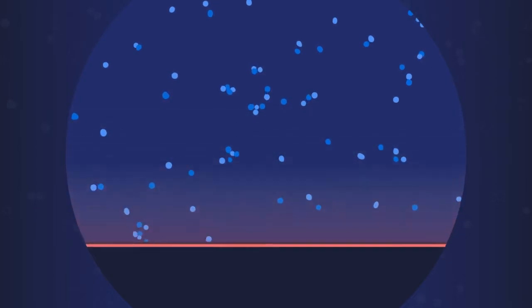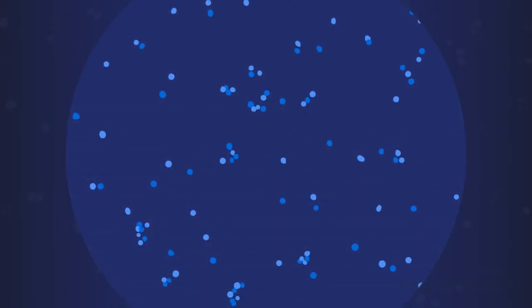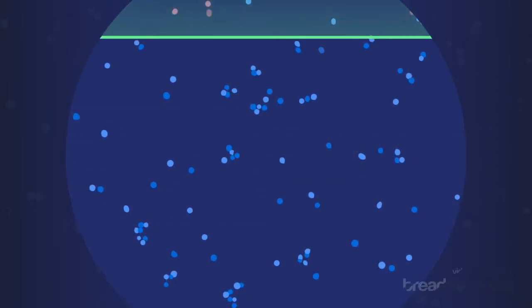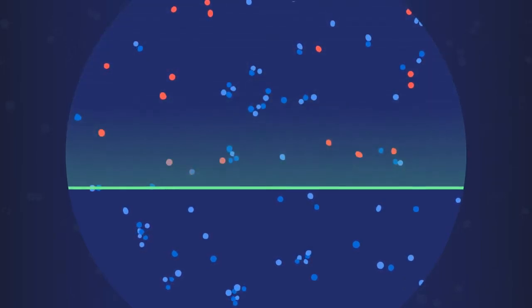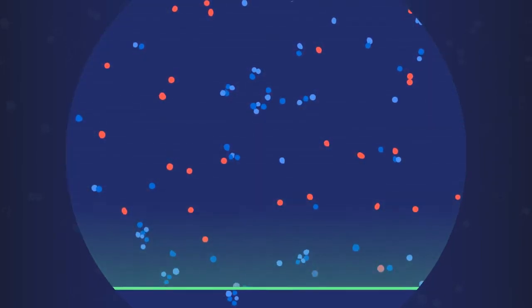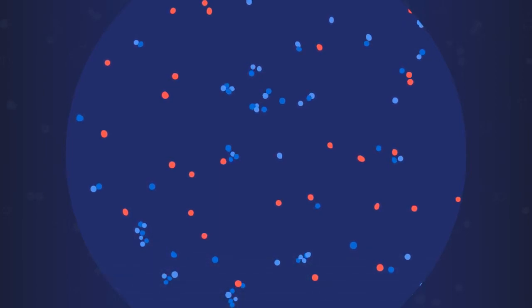Each sample is scanned with two lasers focused to pinpoints much smaller than a single human cell. The fluorescence of each particle, which is proportional to the biomarker concentration in the sample, is then measured without illuminating any of the surrounding fluid.